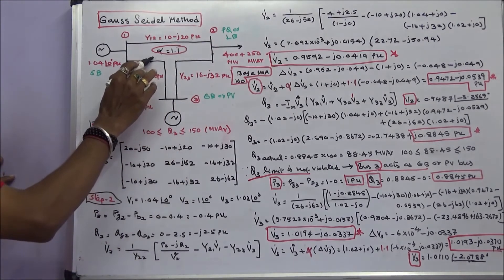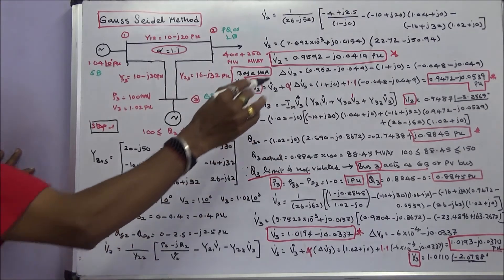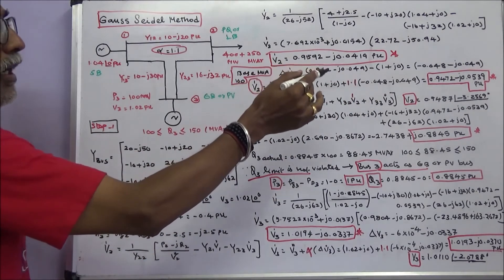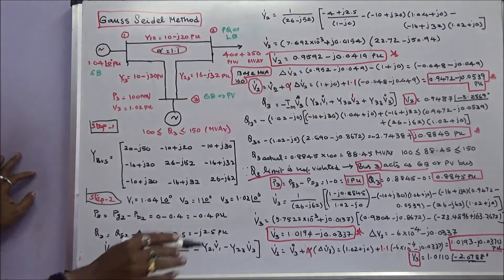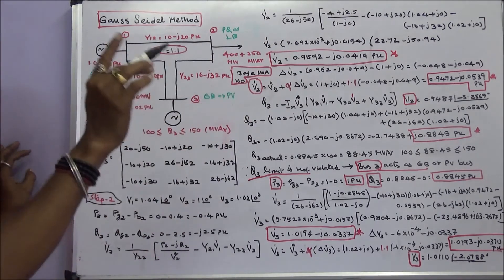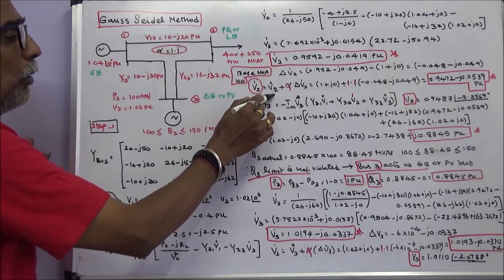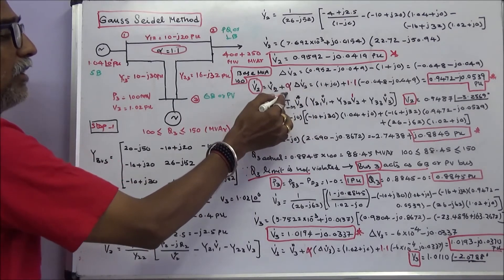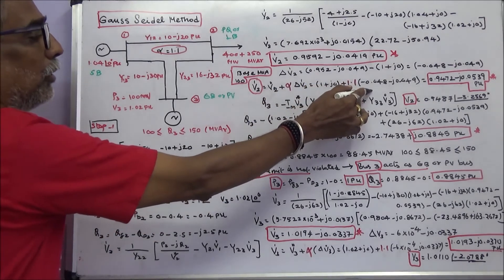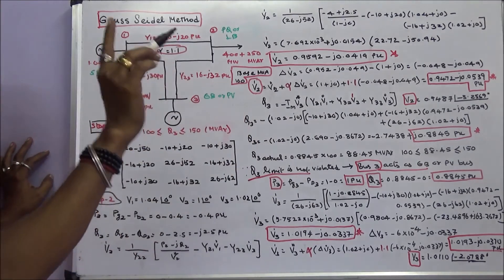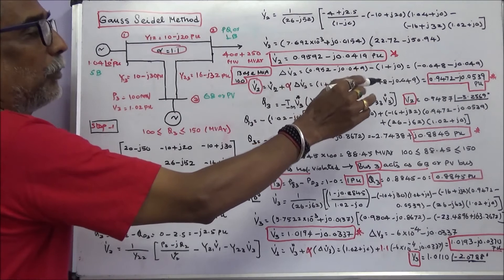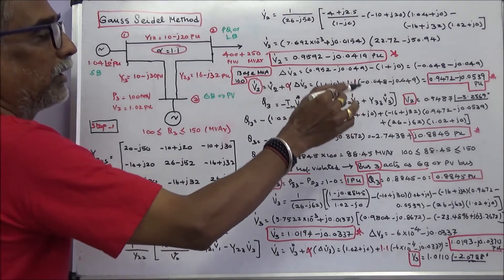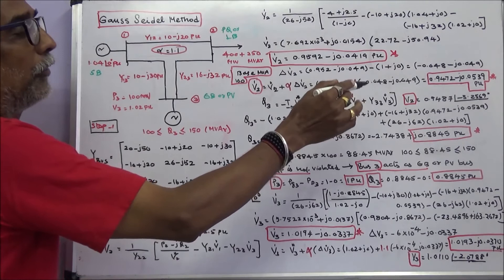The acceleration factor is given as 1.1. The difference between the calculated value and the assumed value is −0.0480 − j0.0419. The accelerated first iteration value is: V2_initial + acceleration_factor × difference = (1 + j0) + 1.1 × (−0.0480 − j0.0419). The accelerated V2 first iteration value is 0.9472 − j0.0539 per unit in rectangular form, or 0.9487∠−3.2569° per unit in polar form.